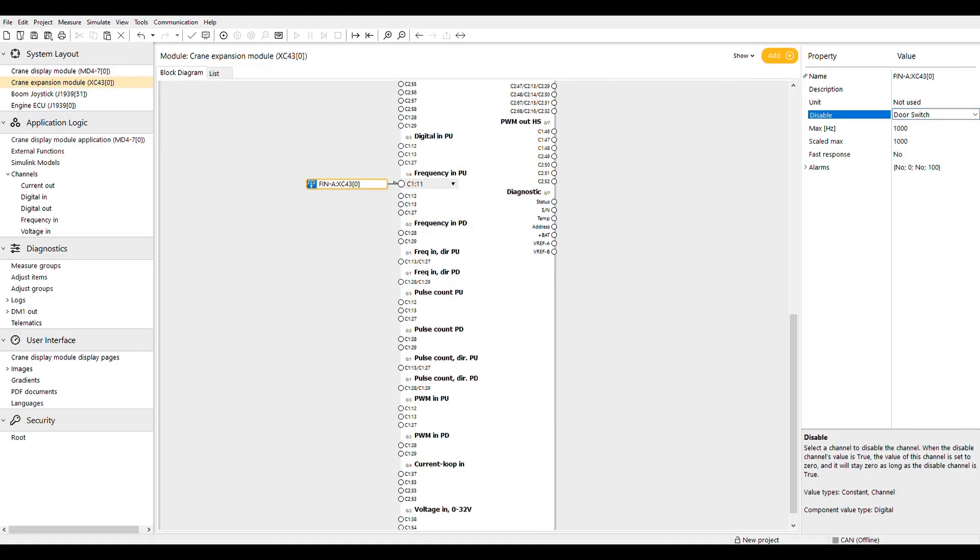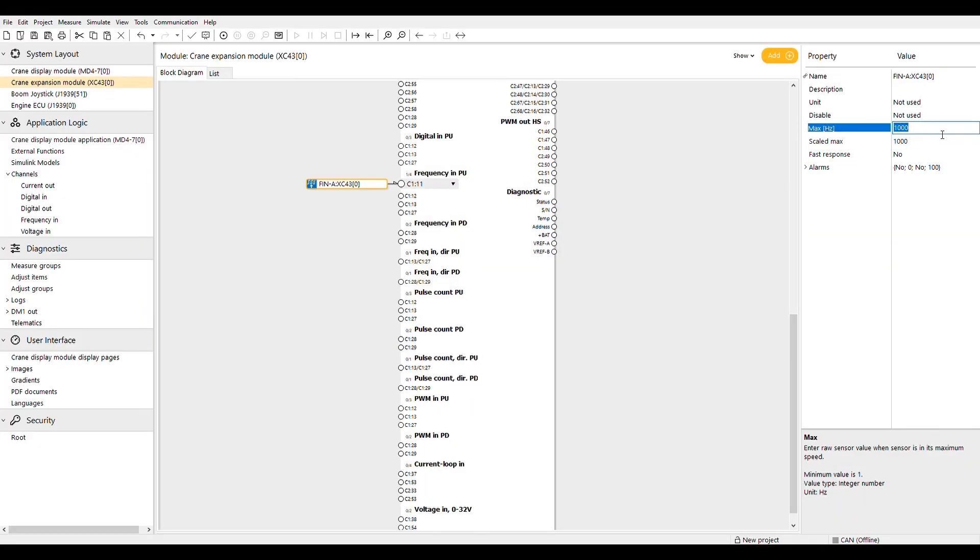The frequency inputs have a range of 5 to 50,000 Hertz. The fast response field will consider anything less than 20 Hertz to be zero in order to better use the bandwidth if switched to on.